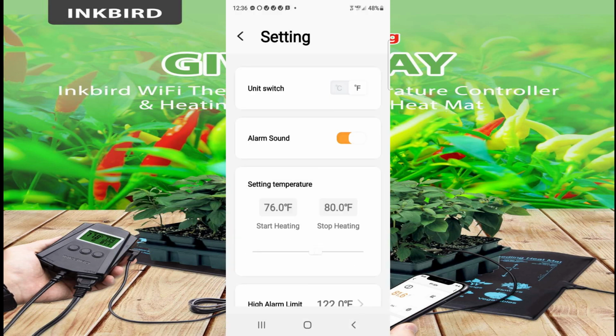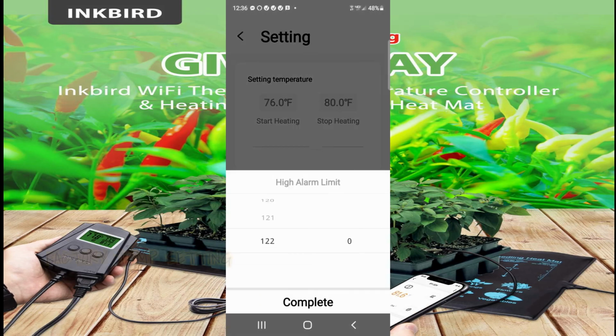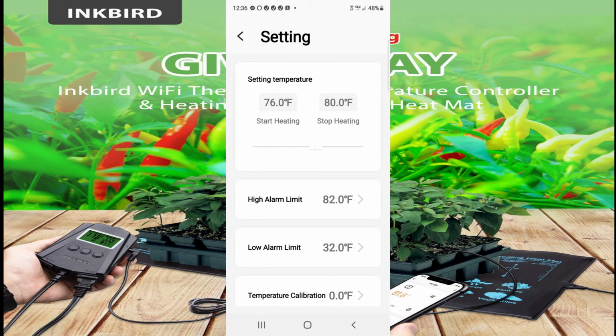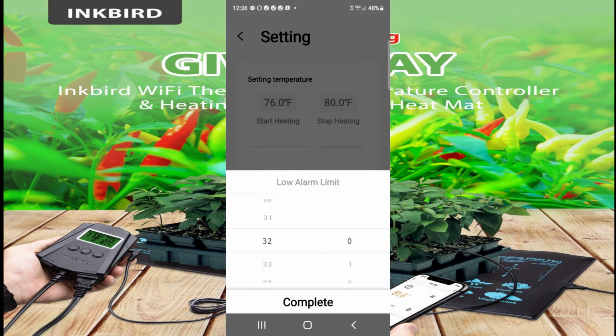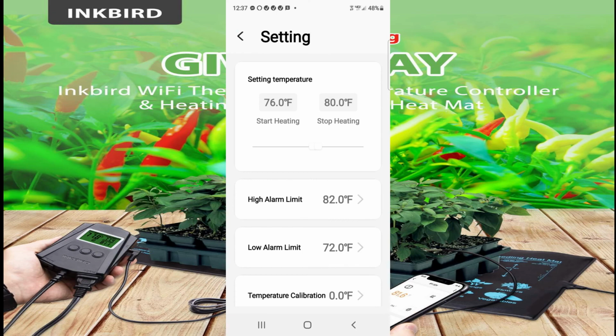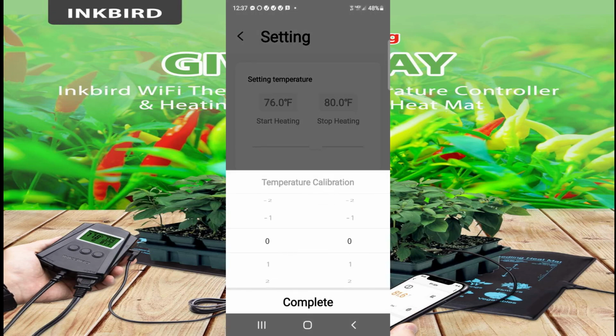Back to 80 degrees. Now we're going to set the alarm high limit, obviously not 122. So we're going to take it back down to, let's say, 82 degrees. And complete. And now the low limit, this is a factory setting at 32 degrees Fahrenheit. I'm going to go ahead and take that up to, let's say, 70 degrees. So if it ever gets down low, we'll go 72 degrees. If it ever gets down that low, it'll send me an alarm.